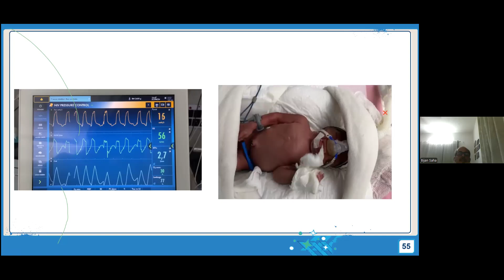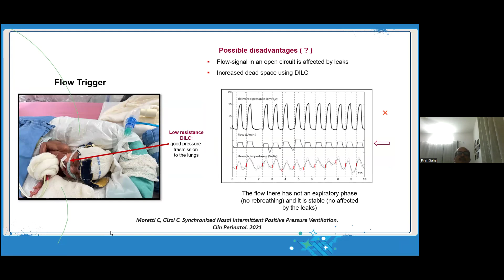Next slide. So what happens if there is no triggering? What will happen if the breath is not triggered? Trigger means when the patient is taking a breath, at the same time the ventilator is also delivering a breath. If it happens that way, more tidal volume will be delivered. But this is not possible. Flow signal in an open circuit is always affected by leak and increased by dead space. Next slide, please.